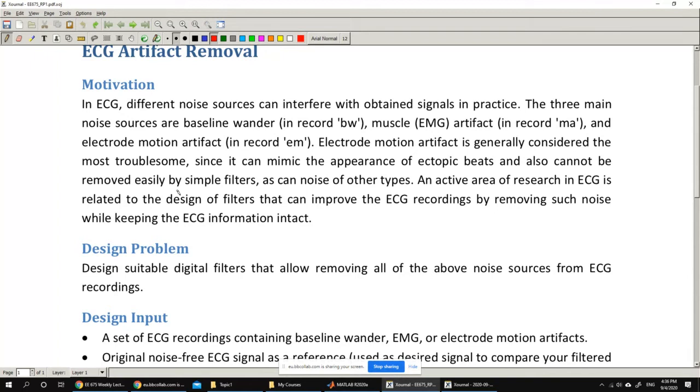It's very difficult for us because we're not medical doctors. Usually what we know is how to design an ECG, how to build an amplifier that would take an ECG signal from a patient, filter it and amplify it to a particular level so that you can either print it or acquire it inside a computer and display it. Other than that, we don't really know what ECG should look like, apart from the very famous drawing of the ECG, which is actually not exactly how it should look in all the channels. So we don't really know how to even describe what the artifacts would look like.